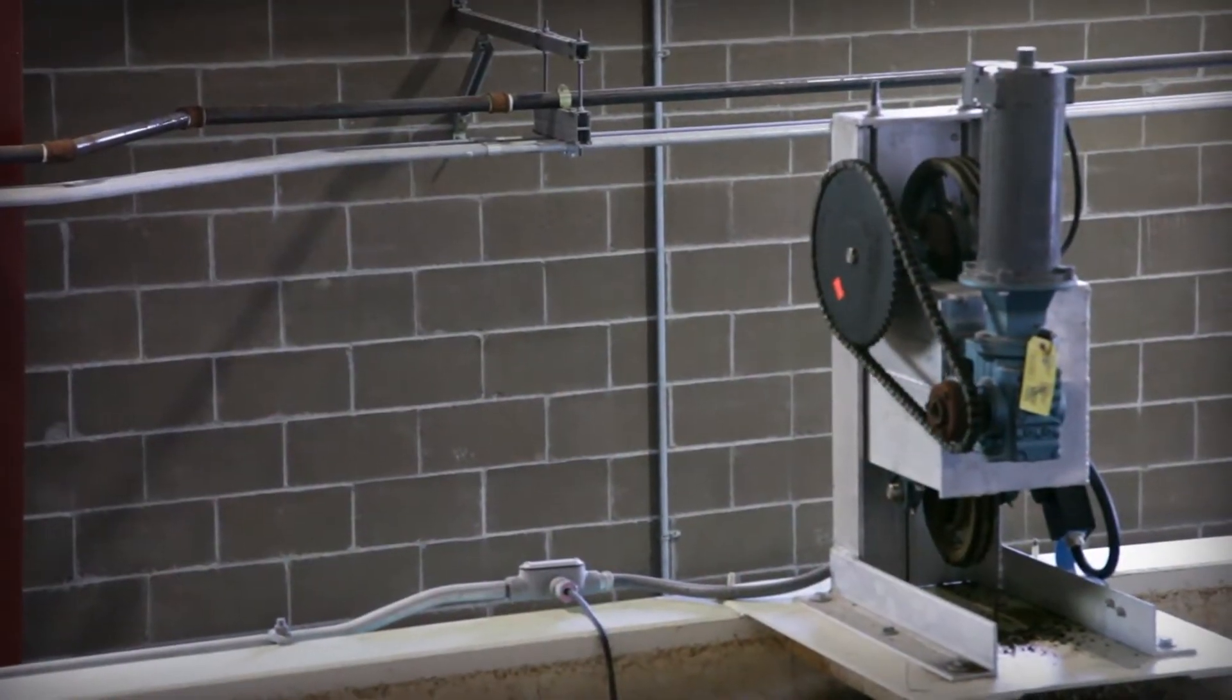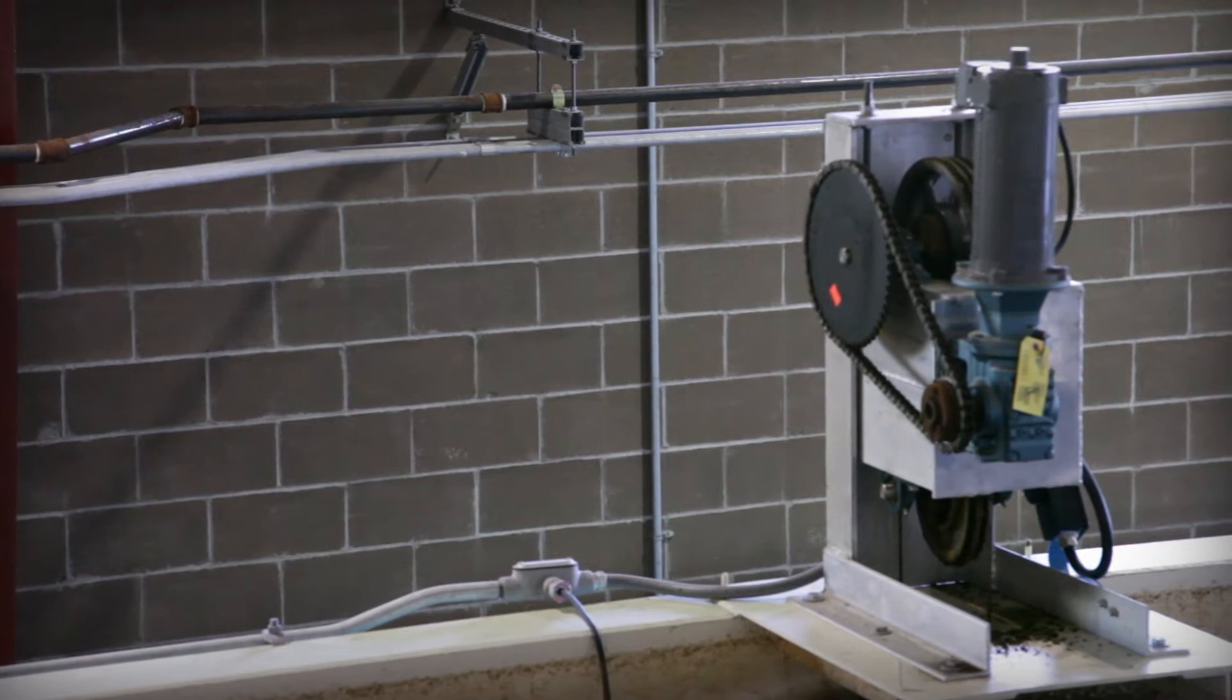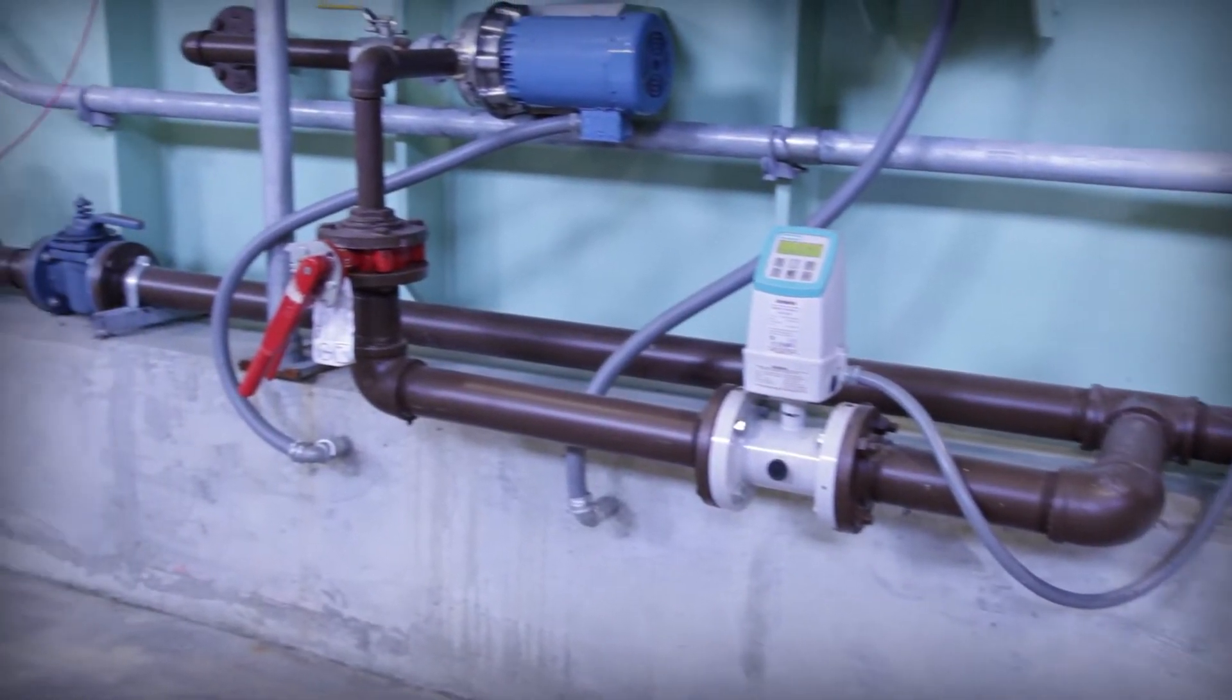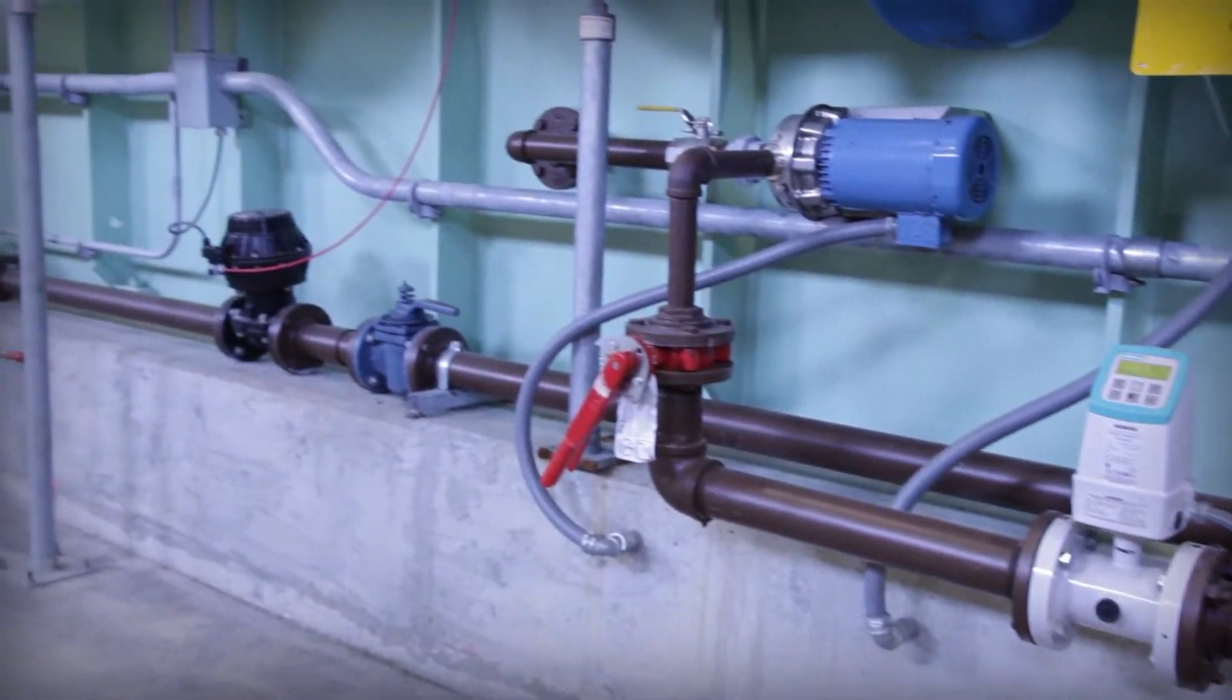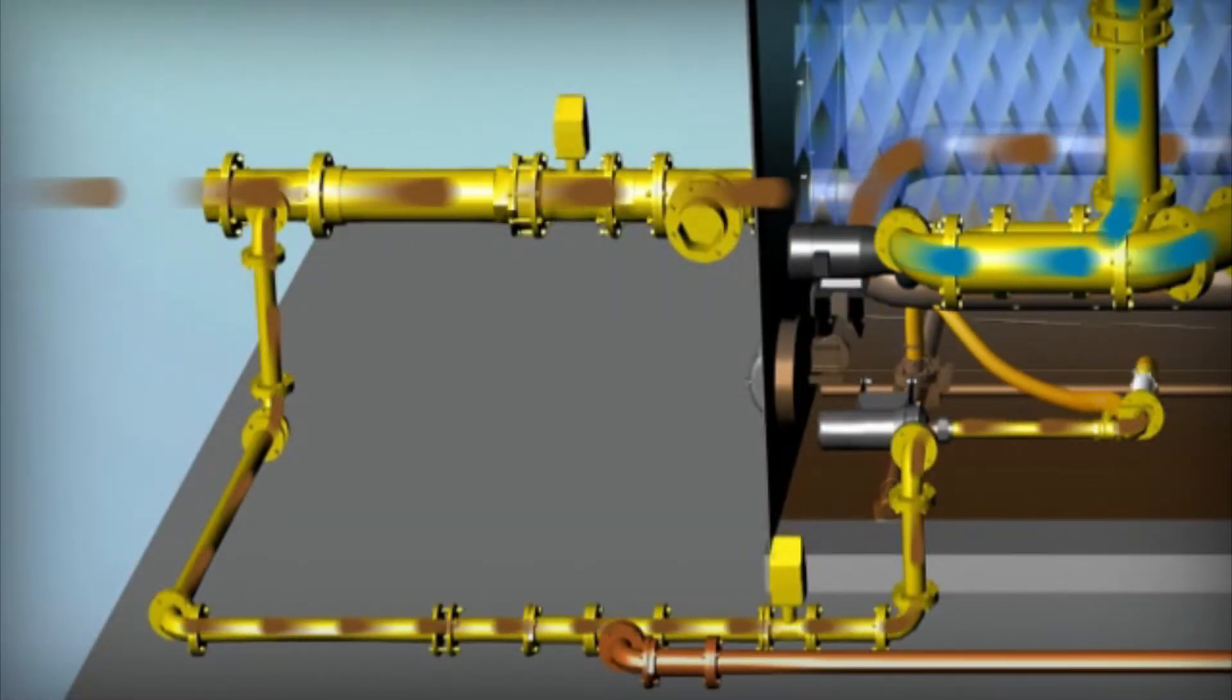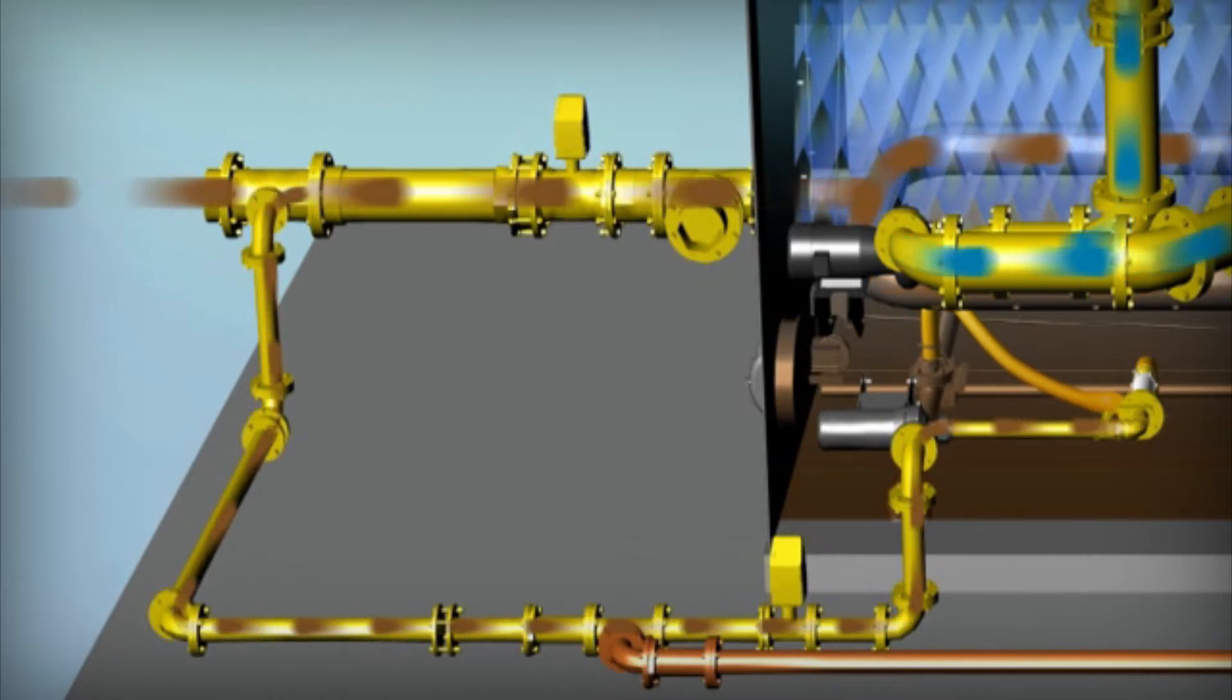Coagulant and polymer are added to the raw water to begin the flocculation process. A small amount of sludge is recirculated from the tube clarifier and mixed with the incoming raw water. This aids in rapid floc formation and dampens variations in the raw water.